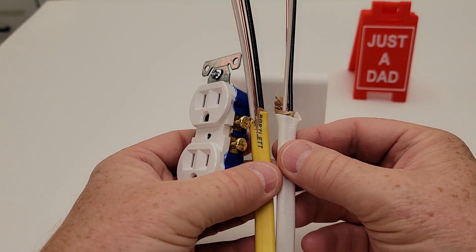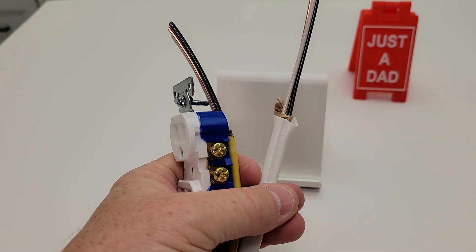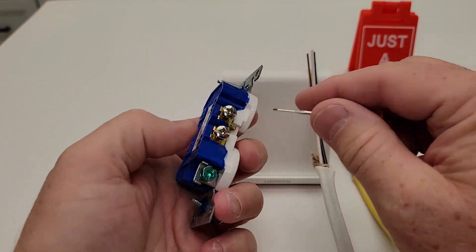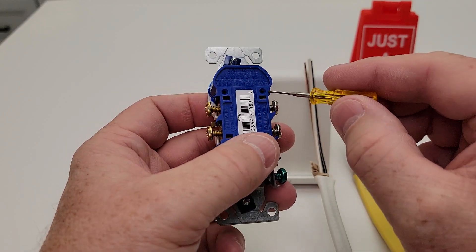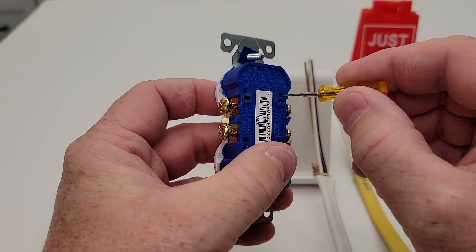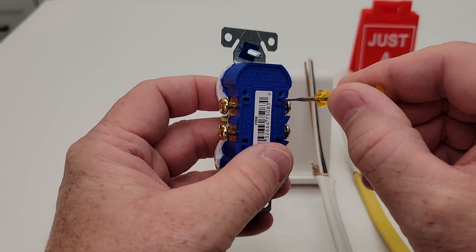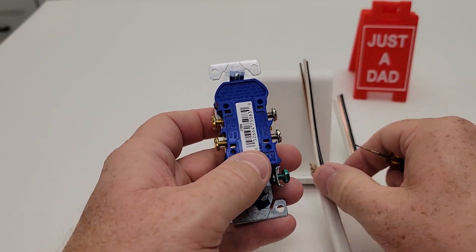Here I've got two different sizes of wiring: 12 gauge and 14 gauge. There's two ways you can install the wires. You can wrap them around the screws and tighten the screw. But if you've got 14 gauge wire, you can insert them in this little hole right here and friction fit will stay in there. If you want to take it out, you can put a little screwdriver in here and pull the wire out.